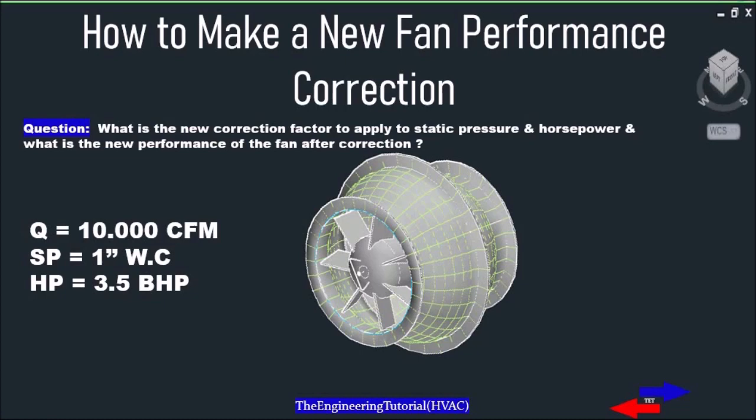it's just more or less dense depending on altitude and temperature conditions. Let's say we have selected a fan which operates at standard conditions — 70 degrees Fahrenheit at sea level — and it is capable of delivering 10,000 CFM of air at a static pressure of 1 inch of water column with a brake horsepower of 3.5.